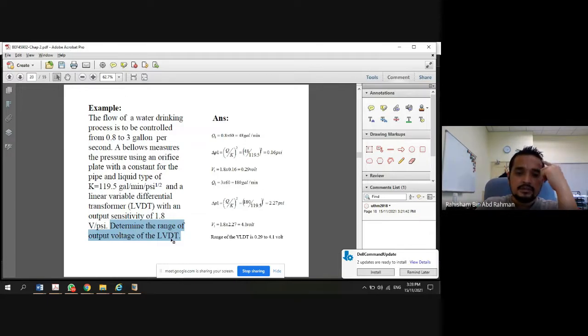Okay, what is the range of this one? We want to know exactly what the range is for this LVDT for each particular application. Maybe from 0 to 5, maybe from 0 to 50, and maybe from 0 to 100. Of course, when we use a very wide range, we need to compromise on the sensitivity. If we go for a very narrow or small range, for example 0 to 5, the sensitivity will be increased, and maybe we can measure in terms of 2 decimal places and even more. Okay, so that is with regard to this one.